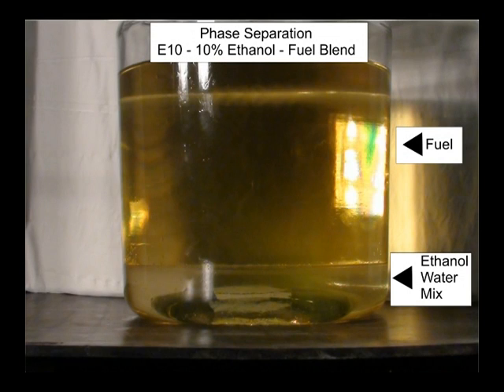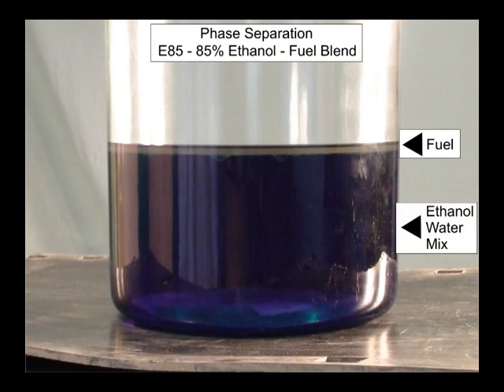Phase separation. Phase separation occurs when water in a tank is absorbed by ethanol in an alternative fuel blend. As the blend becomes saturated, the water will fall out of solution, bringing with it the attached ethanol molecule. The result will be a distinct layer of gasoline floating on the ethanol water layer.